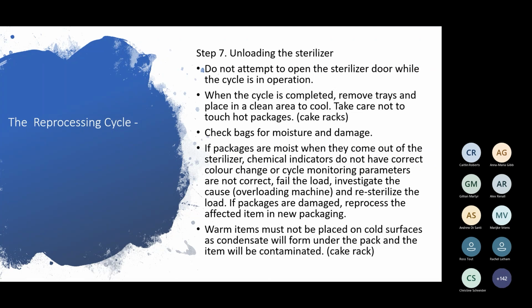Just as an example, for load capability of a machine, a 23-litre MELAG can process 6 kilos of instruments when they're unwrapped. But as soon as you wrap those instruments, the load capability goes down to 2 kilograms. So it drops from 6 kilograms unwrapped to 2 kilograms wrapped. That's a big difference, and that's why you need to know what your machine is capable of. Warm items must not be placed on cold surfaces. I just said that because we're going to get condensation.